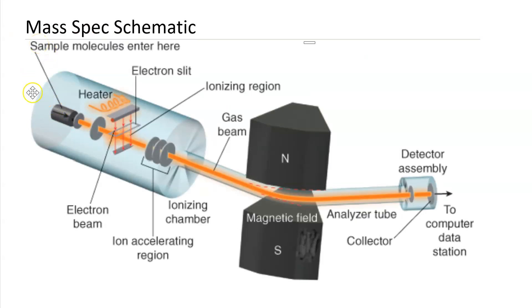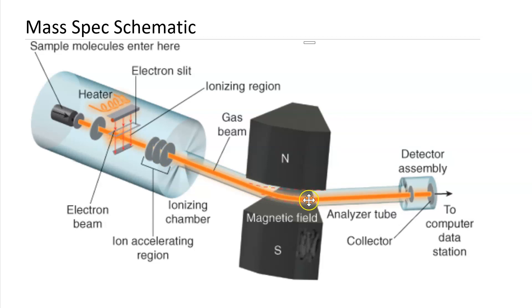Here's a mass spec schematic. Sample molecules are injected, then they're heated by a coil and passed through a slit. Then the electron beam is passed through the sample beam, and ionization and fragmentation takes place there. Then a series of charged plates with a slit in them cause acceleration of the fragments, and so the fragments pass through a magnetic field.